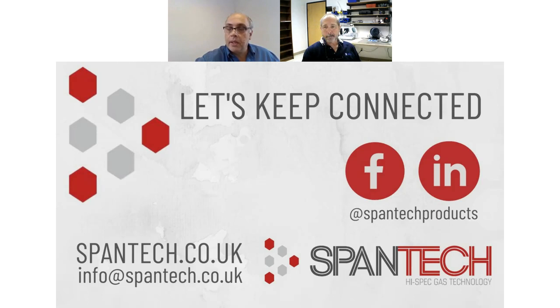Okay, the next one I think is for the ozone generator. Can I have one fixed flow with fixed ozone ppm generating, and variable flow with variable ppm outputs? What are the limits in the case of the Genie, which I believe are factory set at the time of order placement? That's right. The ozone generator is a little different from the other generators in that we send a fixed amount of energy to the lamp all the time. The way we vary the output, the standard unit lets you select between 0.2 and 1 part per million, and we increase the flow rate to give you less ozone. If you set the ppm level to 0.2, the flow rate is 1 liter per minute. If you set the concentration you want to 1 ppm, the flow is 0.2.